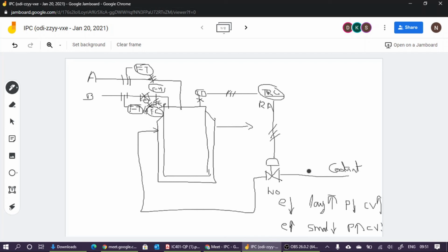Now what we are doing in order to avoid this saturation, you can see that normally if there is no saturation, this feed flow rate controller is sufficient. There is no need to change the flow rate of feed. That one is a free variable. Flow rate of feed A is a free variable, and we are changing the flow rate of feed B with respect to the flow rate of feed A. This is sufficient under normal situation.